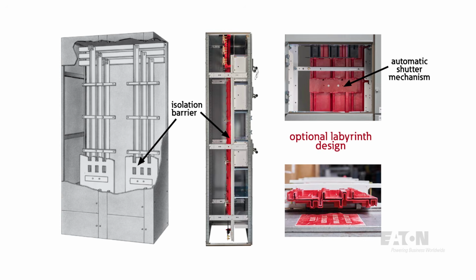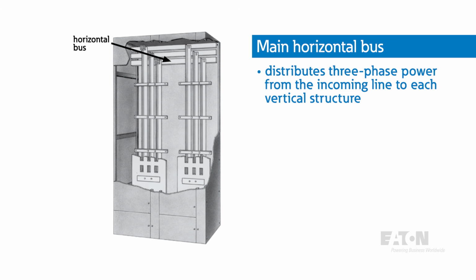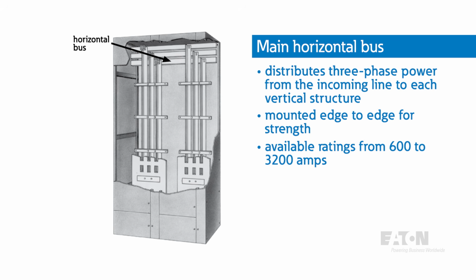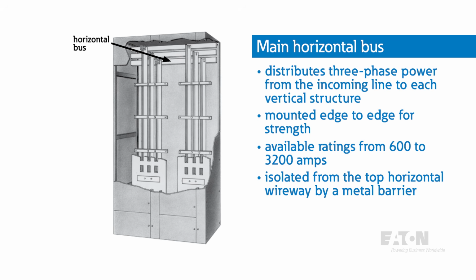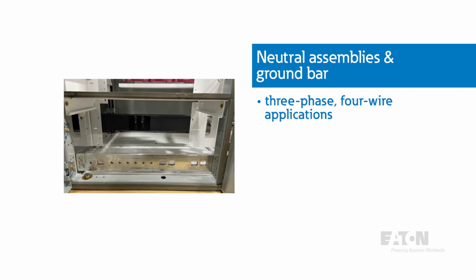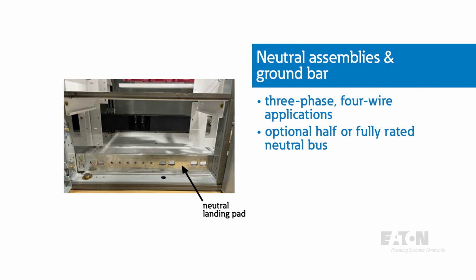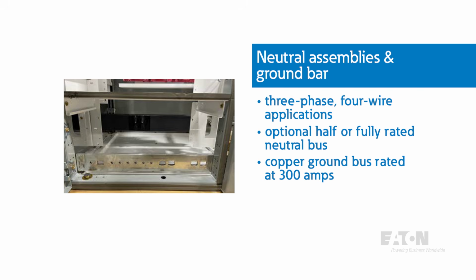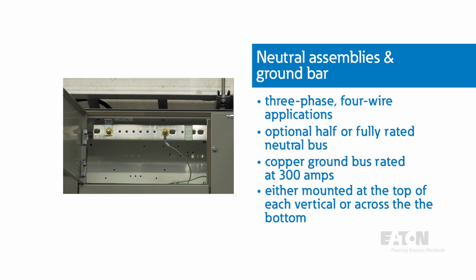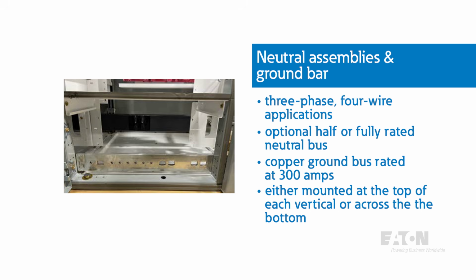The main horizontal bus distributes three-phase power from the incoming line to each vertical structure. It is mounted edge to edge for strength and is available in ratings from 600 to 3200 amps. The bus is isolated from the top horizontal wireway by a metal barrier, allowing easy access for maintenance. For three-phase, four-wire applications, a neutral landing pad is provided. Optional half or fully rated neutral bus can be supplied. A copper ground bus rated at 300 amps is mounted across the top of each vertical structure as standard, or can be mounted across the bottom when the bottom 9 inches are not occupied by units or master terminal blocks.